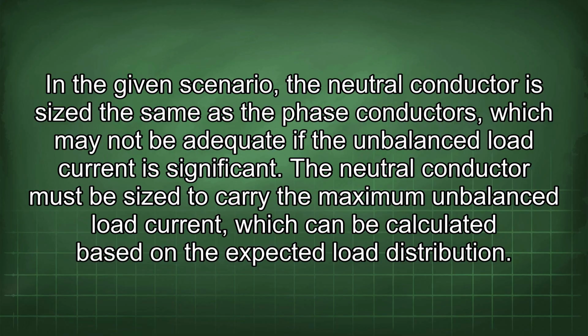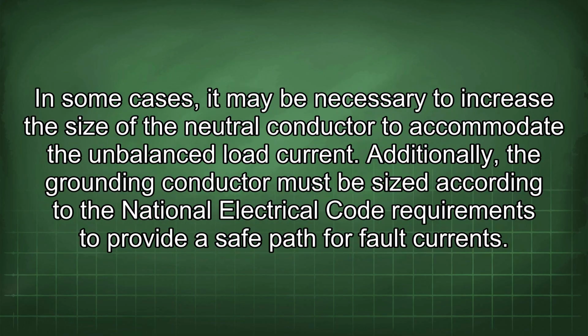The neutral conductor must be sized to carry the maximum unbalanced load current, which can be calculated based on the expected load distribution. In some cases, it may be necessary to increase the size of the neutral conductor to accommodate the unbalanced load current. Additionally, the grounding conductor must be sized according to the National Electrical Code requirements to provide a safe path for fault current.